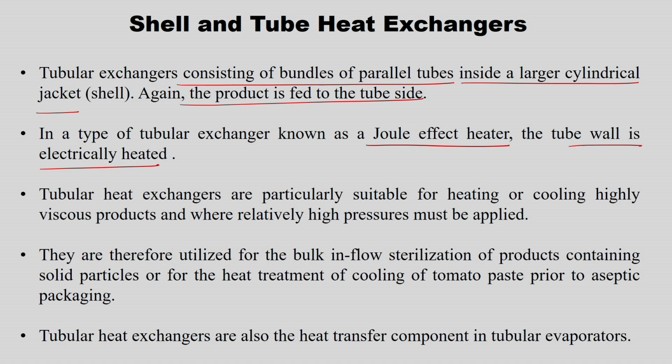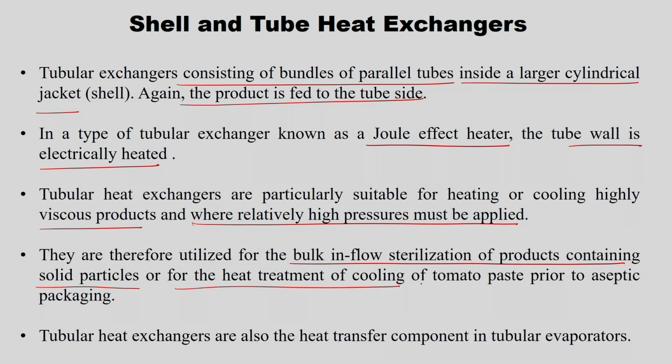The tubular heat exchangers are particularly suitable for heating or cooling highly viscous products where relatively high pressures must be applied. They are also utilized for in-flow sterilization of products containing solid particles, and for the heat treatment or cooling of tomato paste prior to aseptic processing.